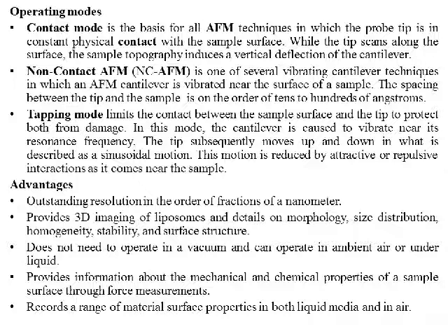The third operating mode of an AFM is tapping mode. In tapping mode, the sample surface and the tip are both protected from damage. The cantilever is caused to vibrate near its resonance frequency, so the tip moves up and down, similar to a sinusoidal motion.